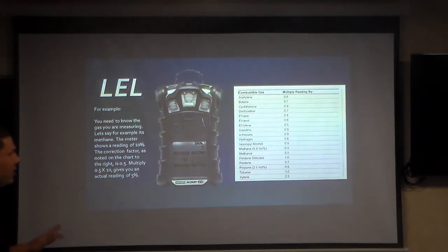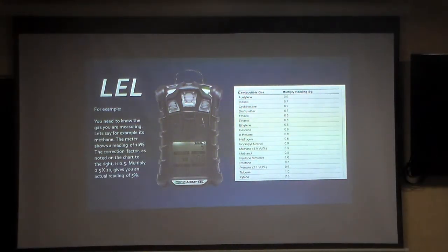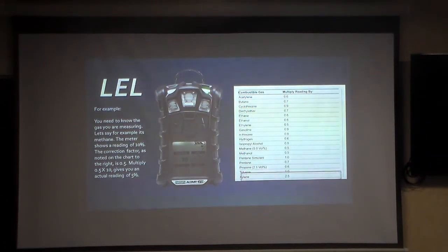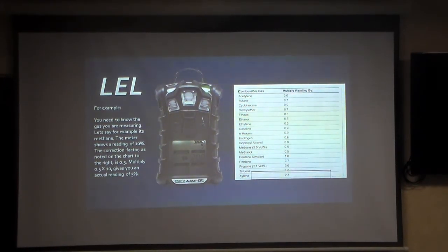What I am concerned about is numbers that are greater than 1. Okay? Greater than 1. And in this case, there's only one, and that's xylene. If you remember that little study that I showed you with the chart that had the 5 most dangerous spilled substances, xylene was one of them. Okay? Our meter is 2.5 times less responsive to xylene than it should be. So if you know that you're metering xylene, that's the one chemical you need to know in order to make sure that you are not in a dangerous atmosphere, or more dangerous than you think it is.